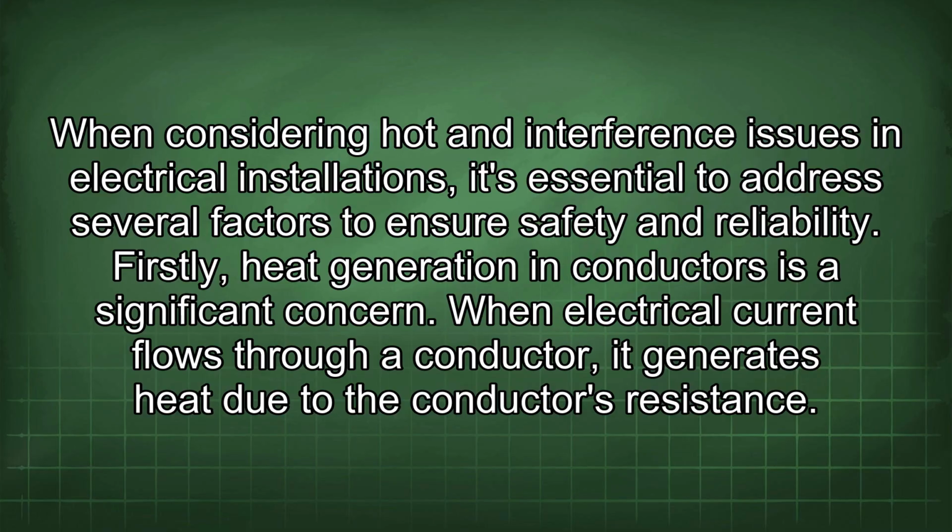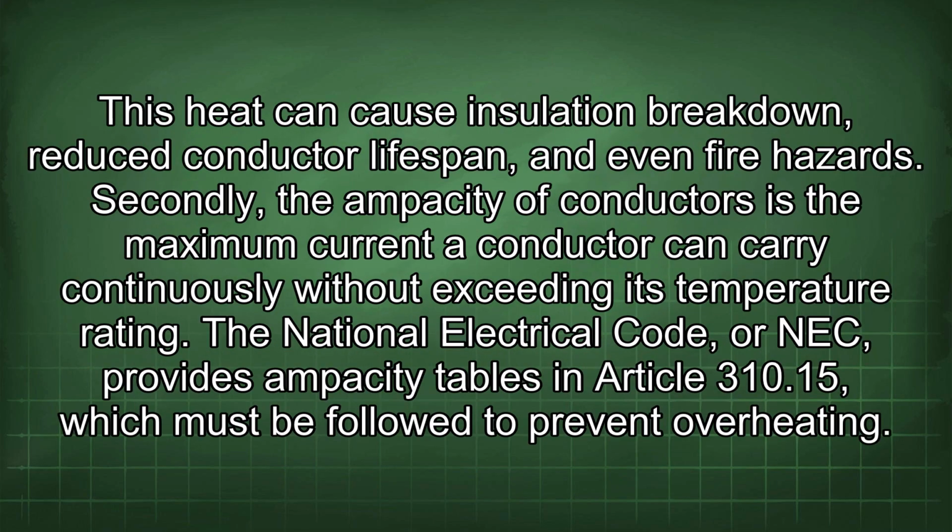Firstly, heat generation in conductors is a significant concern. When electrical current flows through a conductor, it generates heat due to the conductor's resistance. This heat can cause insulation breakdown, reduce conductor lifespan, and even create fire hazards. Secondly, the ampacity of conductors is the maximum current a conductor can carry continuously without exceeding its temperature rating.